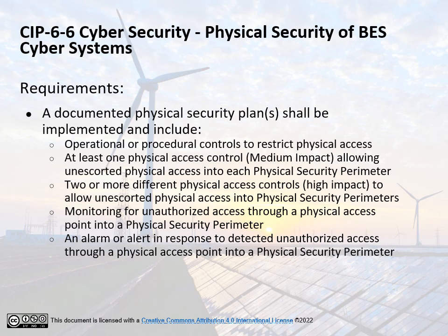physical access point into a physical security perimeter, an alarm or alert in response to detected unauthorized access through a physical access point into a physical security perimeter to personnel identified in the BES Cybersecurity Incident Response Plan within 15 minutes of detection.